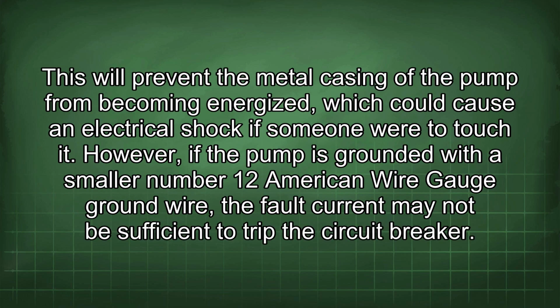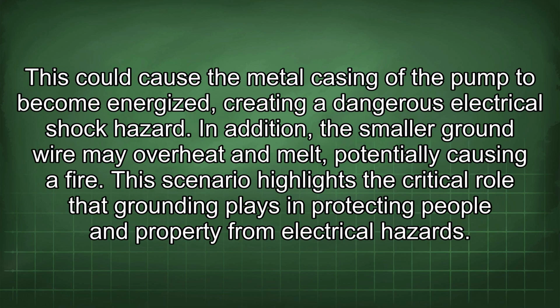This will prevent the metal casing of the pump from becoming energized, which could cause an electrical shock if someone were to touch it. However, if the pump is grounded with a smaller number 12 American wire gauge ground wire, the fault current may not be sufficient to trip the circuit breaker. This could cause the metal casing of the pump to become energized, creating a dangerous electrical shock hazard.